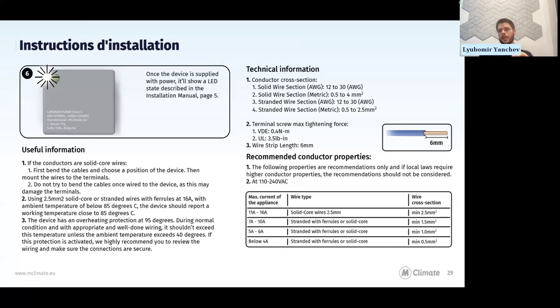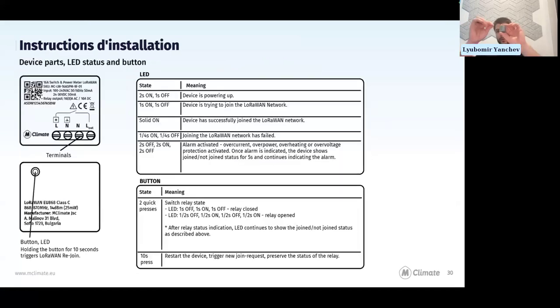In the user manual we also include a table of recommended cable types. In our stress tests we tried all types, including passing 16 amps through a 1 mm² cable just to see how and when the device would fail, and we confirmed that with 1 mm² it will fail. With this small cross section, electricity textbooks say you need at least 1.5 or 2.5 mm², but depending on national legislation, pick and choose well, and screw the terminals properly.